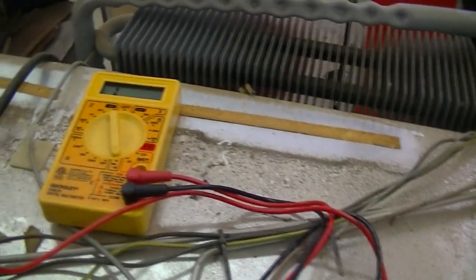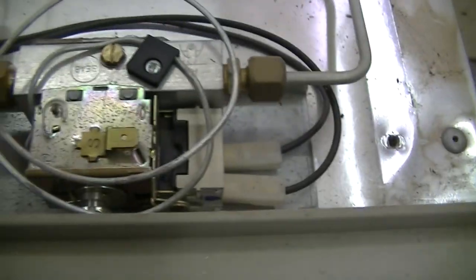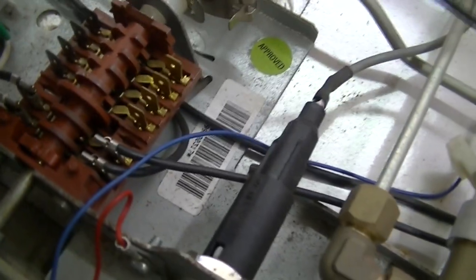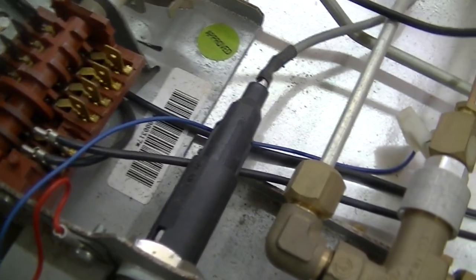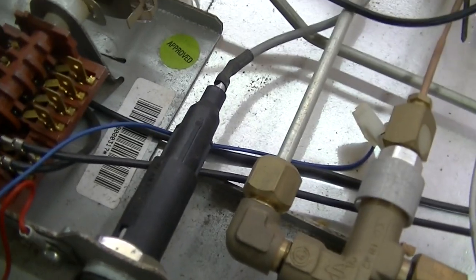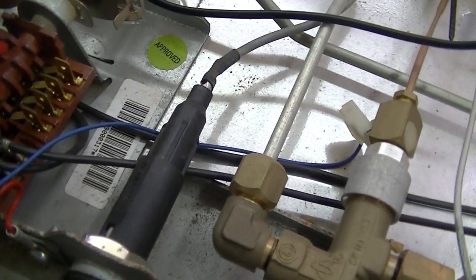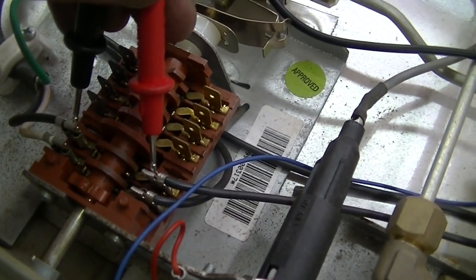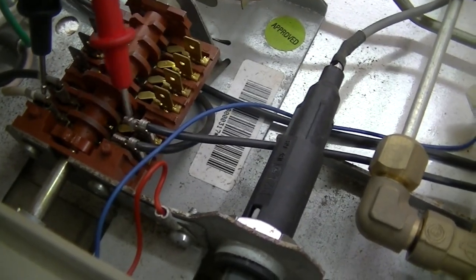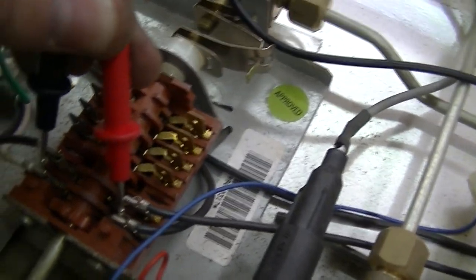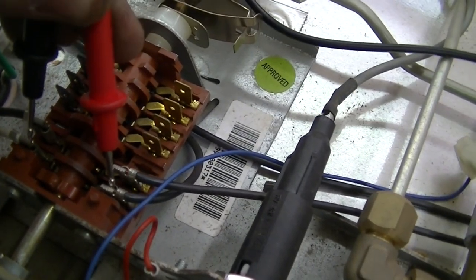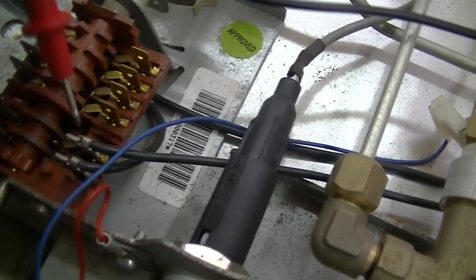Okay, so I've identified the problem. The thermostat is actually good. The problem lies here in this main power switch, which I thought would be okay because mechanically there isn't much to it, but I was wrong. So as you can see, there's continuity here. The switch is in AC mode by the way. I got nothing here on the neutral. Got hot though, we don't got neutral. So I'm gonna have to take it apart I guess and see what's going on.